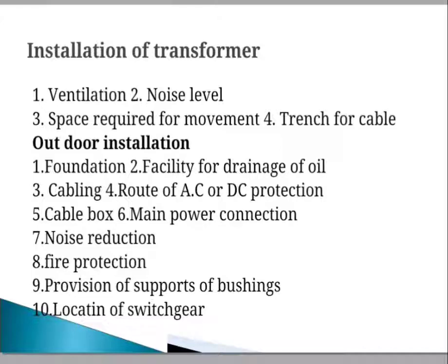The third factor is the cabling. Power cables and control cables should never be placed in the same conduit. DC control cables, AC protection circuit cables and AC power cables should be separated from each other, so that interference does not happen between them.